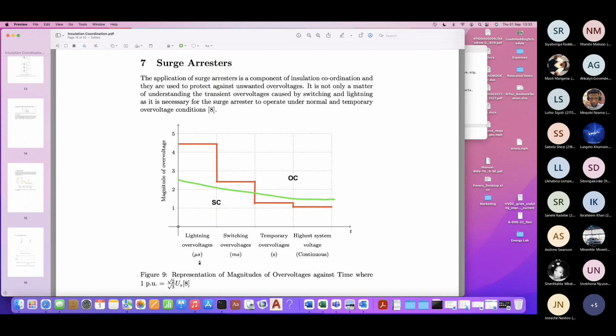Right, okay. So for the lightning overvoltages and switching overvoltages, you want to conduct all the way to earth. It's not an ideal short circuit, it still has an impedance, so there are characteristics to it. You want to cap the voltage, you saw that characteristic earlier, such that it doesn't exceed the lightning impulse withstand level, or BIL, for the lightning overvoltages. Or the switching impulse withstand level for the switching overvoltages.